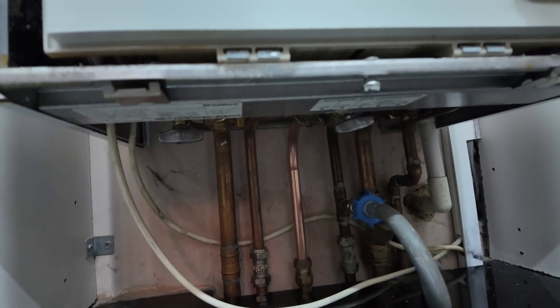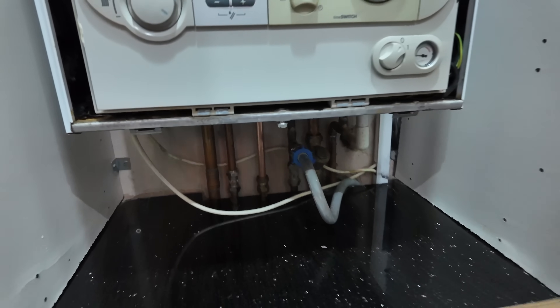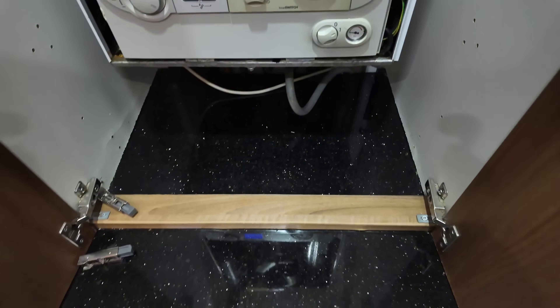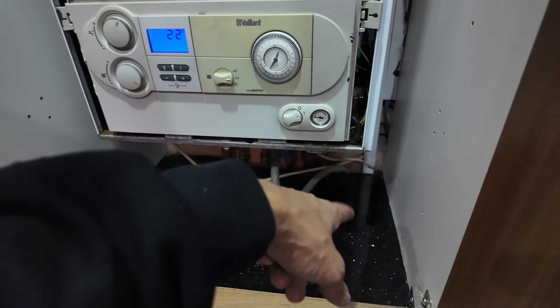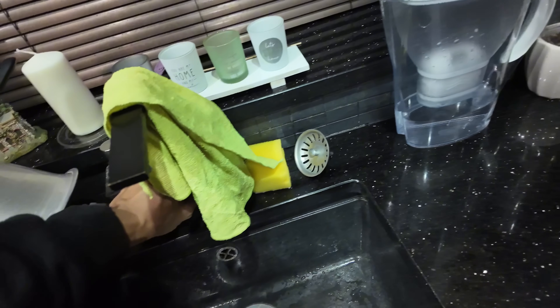What I've actually done is bent a bit of 15mm pipe — couldn't be bothered putting extra compression fittings on, so I just went to the back of the van, bent a bit of pipe, and we've got one clean joint on there. I've just done a drop test — that's sound. The analyzer is purging. Let's put the boiler on and find this carbon monoxide leak. There's still a bit of residual water from the back of the boiler but it has stopped leaking now, so I'm going to get a few little drips as it clears. Let's run a hot tap.